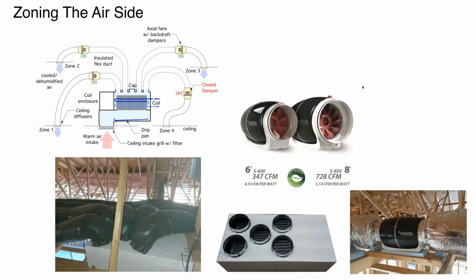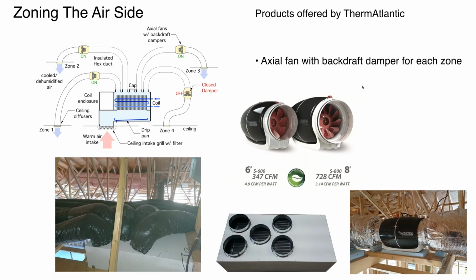Here's another interesting approach. There's a company up in Canada called Thermatlantic, and what they're doing is basically they're putting a coil into a container, a sheet metal box, but there's no blower in it. Okay, there is a condensate drip pan, so essentially they're bringing the chilled fluid up to the coil, collecting the condensate, and then they're using these individually controlled axial fans. These are quiet, they're quite efficient. And you can see what they're doing here.